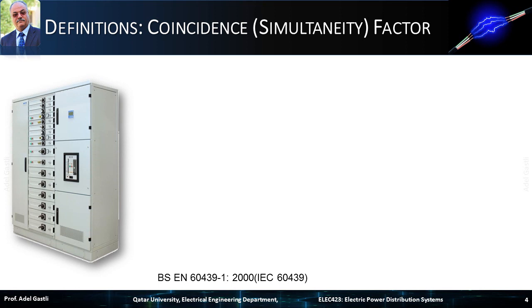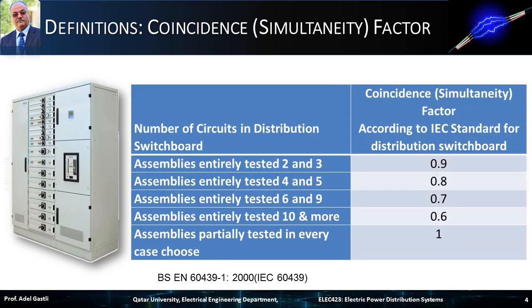Standards such as the IEC have defined some standard coincidence factor values for a distribution switchboard, which can be used by designers when they conduct a load study. This table lists some of these values depending on the number of circuits. IEC classifies assemblies into type-tested assemblies and partially type-tested assemblies. Type-tested assemblies conform to an established type or system without deviations likely to significantly influence performance from the typical assembly verified to be in accordance with the standard; a full range of representative configurations have been tested. Partially type-tested assemblies contain both type-tested and non-type-tested arrangements, where the latter are derived, for example by calculation, from type-tested arrangements which have complied with the relevant tests, and only some limited configurations may be tested.